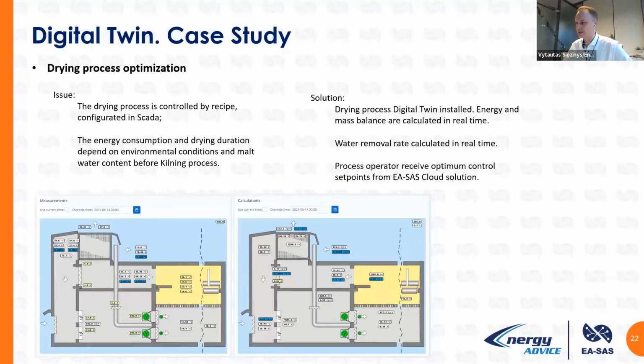So finally, we installed a digital twin solution, and energy and mass balance are calculated in real time. I mean, usually it's during each 5 minutes. Water removal rate calculated in real time, so we understand how effectively water is removing from the malt, and what is the speed, which is very important for example, wood drying. What is the speed of a drying process? What is temperature, water level ratio, in order to have good color requirements or match color requirements, and process operator receive optimum control set points from EA-SAS cloud solution. He just connect to EA-SAS cloud solution and look at the set points, and coming back to the control system, just adjust these according to optimum values.